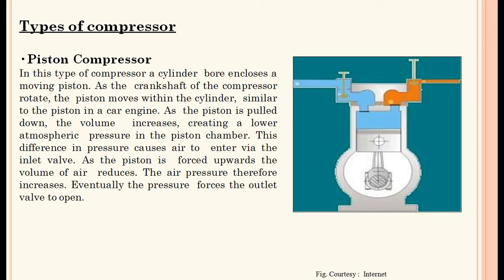Types of compressor: piston compressor — in this type, a cylinder bore encloses a moving piston. As the crankshaft rotates, the piston moves within the cylinder similar to a car engine. As the piston is pulled down, the volume increases creating a lower pressure in the piston chamber; this difference in pressure causes air to enter via the inlet valve. As the piston is forced upwards, the volume of air is reduced and air pressure increases until it forces the outlet valve to open. It is a reciprocating type.